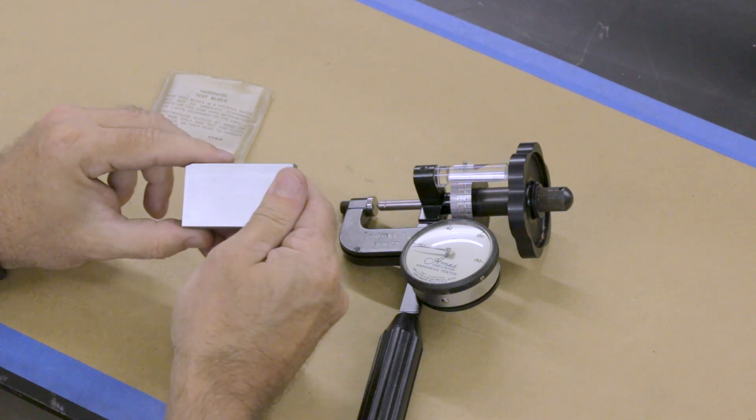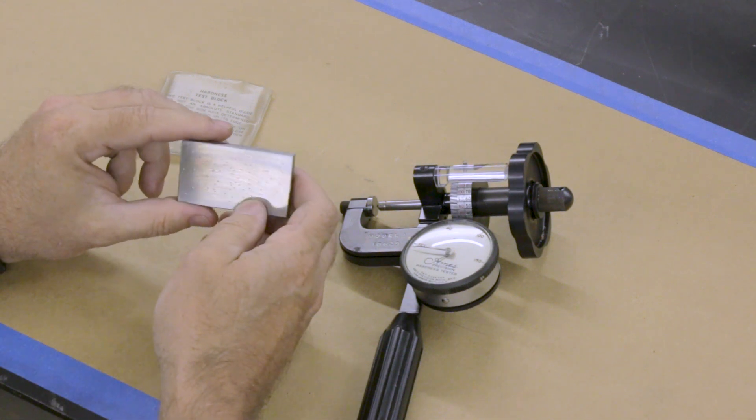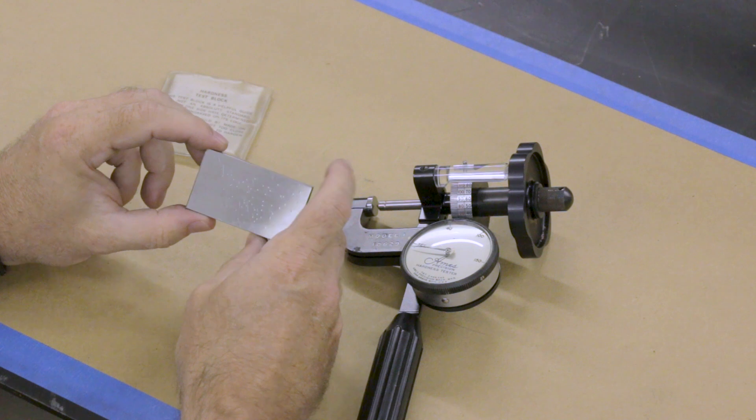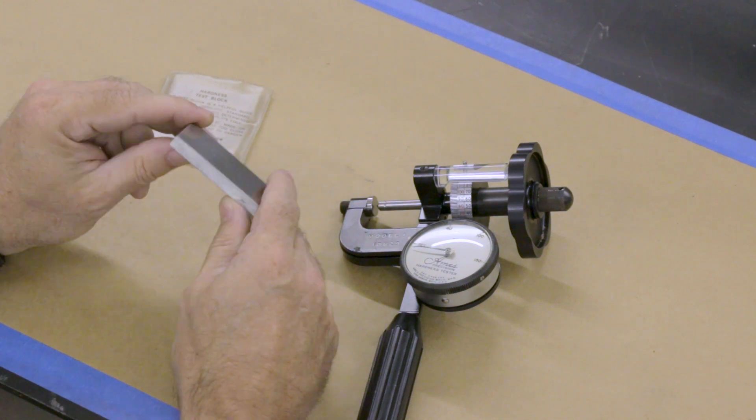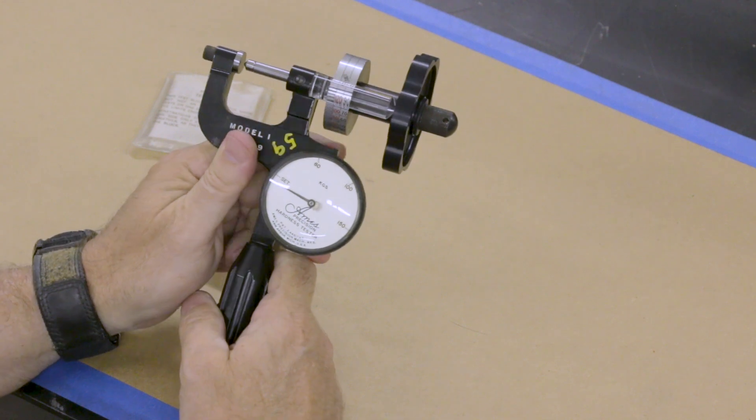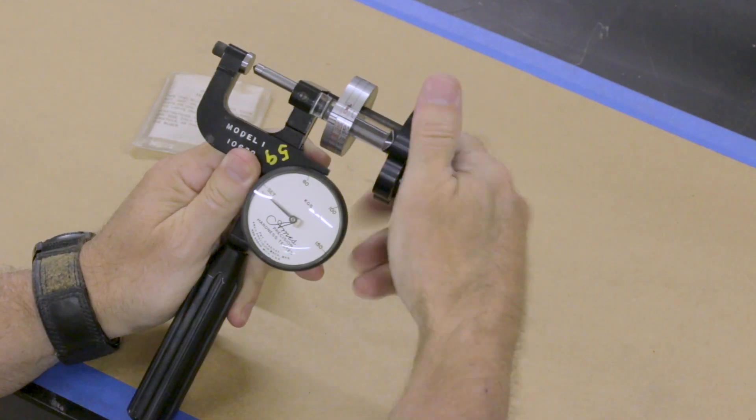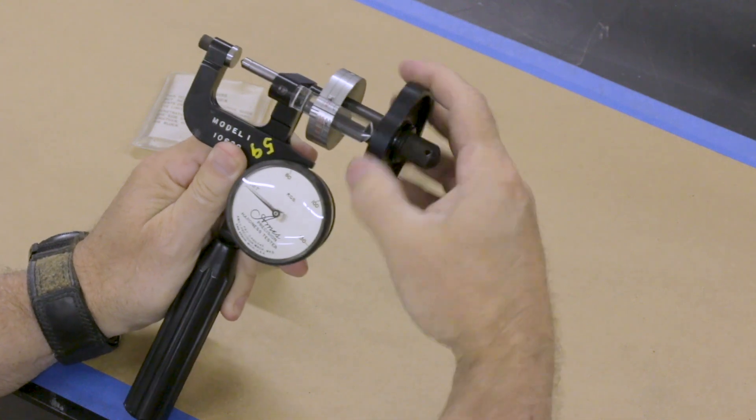So the first thing I do when I use this is I verify my hardness, or I verify my tester on this block, this test standard. The way this works is, first thing I'm going to do is I'm going to open this up far enough that I can get the test standard in it.